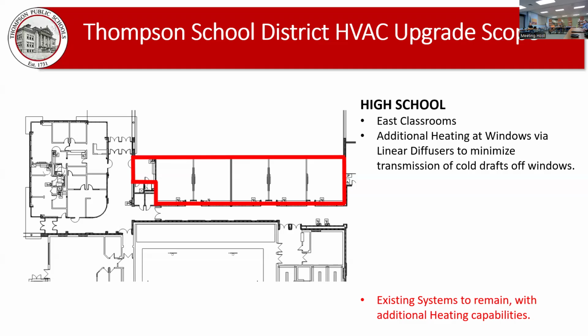So I wish there was something else we could do with them. Just to give an example, where the cursor is right here, there's a supply diffuser, supply diffuser, supply diffuser, supply diffuser, a return diffuser, and a thermostat. So the supply air, as far as it gets into the room, is right here, then immediately goes south to the return, and that movement of warmer air to the return hits the thermostat and the room becomes satisfied.